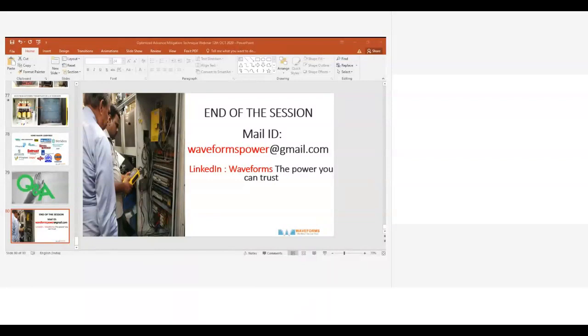If you have a thyristor switch, nothing like it. Or with anti-resonance. But sir, we have recommended thyristor switches somewhere, but these thyristor switches are very costly compared to contactors. Yeah, it is expensive, and it can also cause failure if there is temperature rise and all that. It is almost 7 to 8 times the cost. It is very expensive. But where you have rapidly changing loads, you require this thyristor. That's what, in arc furnaces.